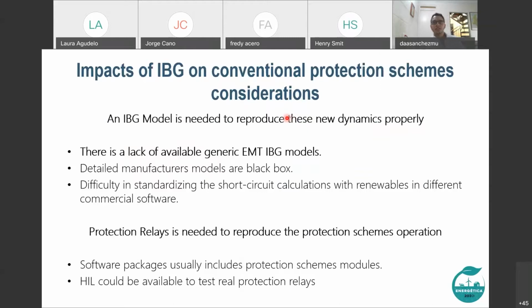So for achieving that general purpose, we need two elements. First, we need an inverter-based generation model which reproduces all these new dynamics properly. Second, we need protection relays to replicate the protection scheme operation. For the first one, we find that there is a lack of generic EMT models. Also, the detailed manufacturer's models are given as black boxes. So that's why we have to build our own generic EMT model fulfilling all the functionalities required for accurate short circuit calculations and protection scheme evaluation. For the second one, we find fewer issues because software packages usually include conventional protection schemes, and we can also use hardware in the loop to test real equipment.